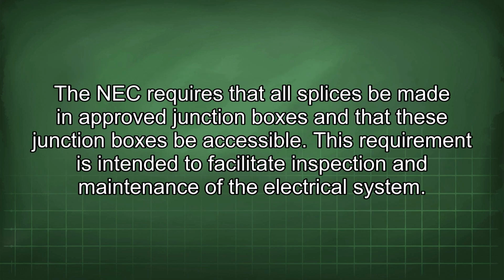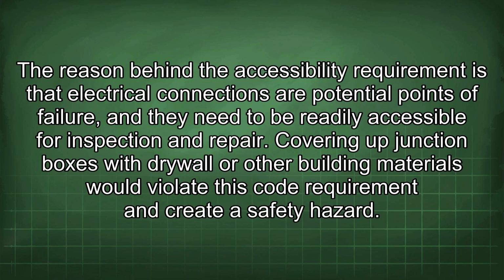The NEC requires that all splices be made in approved junction boxes and that these junction boxes be accessible. This requirement is intended to facilitate inspection and maintenance of the electrical system. The reason behind the accessibility requirement is that electrical connections are potential points of failure, and they need to be readily accessible for inspection and repair. Covering up junction boxes with drywall or other building materials would violate this code requirement and create a safety hazard.